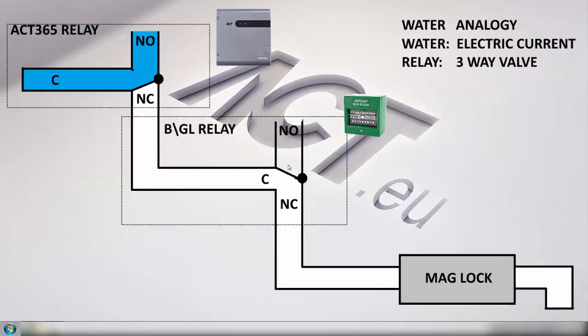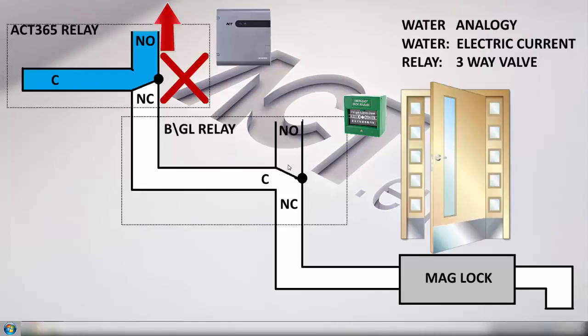But say for example now the state of the ACT365 relay changes. You can see now the current comes in and it flows into normally open so that's connected to nothing. This breaks the circuit and water or the current can no longer flow down into the mag lock causing it to de-energize, hence causing the door to open.